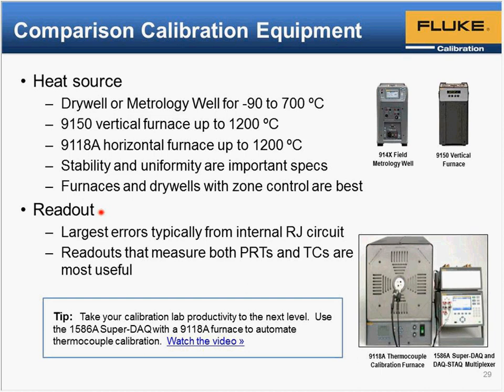Some combined systems, like in this picture in the lower right-hand corner, have a furnace designed to work with this readout, and they connect together so the readout will actually control the furnace and take readings on the thermocouple. It has the built-in math to automatically convert voltage to temperature for you, and has lots of channels. But the advantage is it also measures PRTs, so you have the option of bringing in a reference grade PRT. We'll talk about that next, on reference probes.